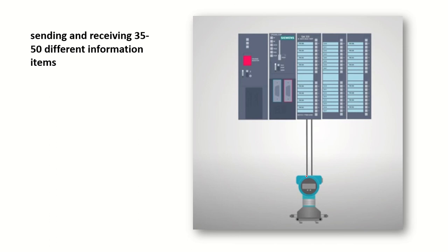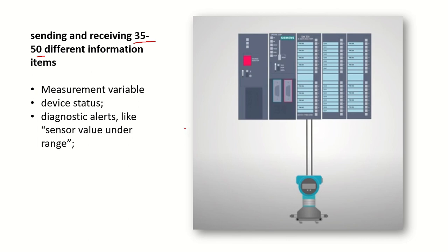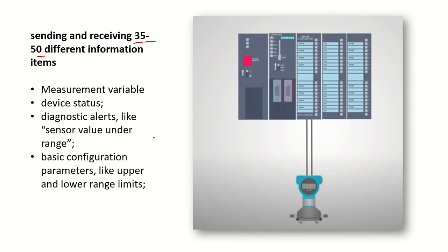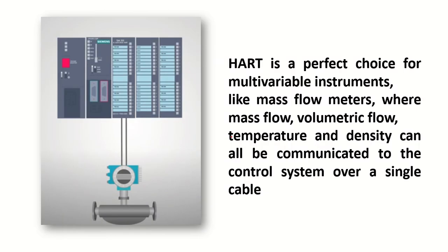Along with the analog signal, around 35 to 50 different pieces of information can be sent. These include the measurement variable, device status (whether the device is on or off), diagnostic alerts such as whether the sensor value is in range or exceeding range, and basic configuration parameters like upper limit, lower limit, and tag name of the device. HART is also multi-variable: for example, a HART flow meter can communicate mass flow rate, volumetric flow rate, temperature, and density — all over a single communication loop.